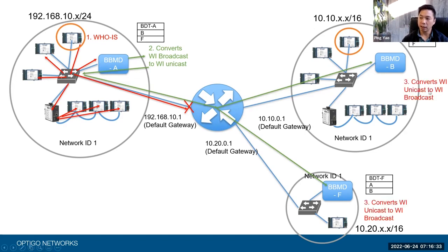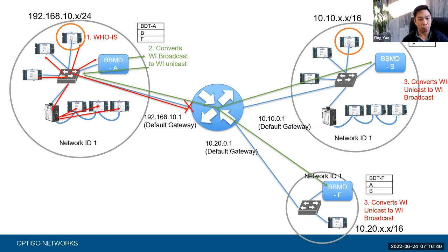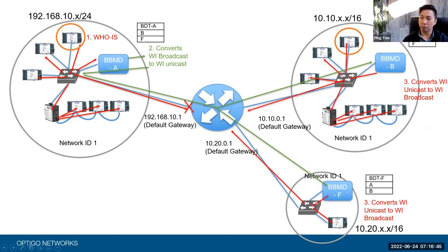B will catch it and say: now I've got to do the reverse function. I'm going to take this unicast message, convert it back into broadcast, and dump it on my network. It will convert it back into broadcast and send it to all the devices on this network. Again, it will reach the IP router, but the IP router will block it. Voila — this is what a BBMD does.